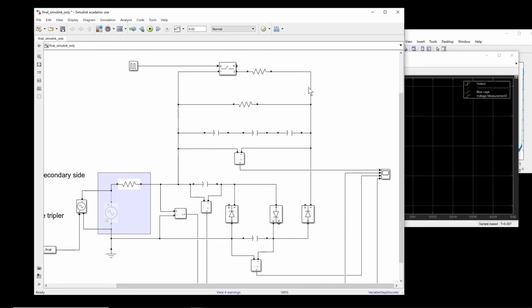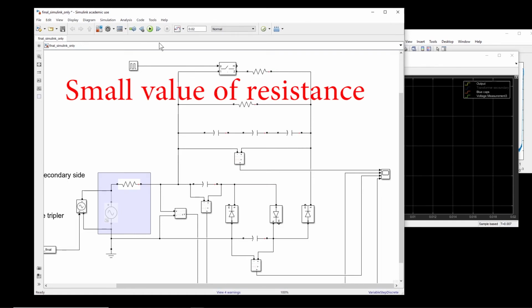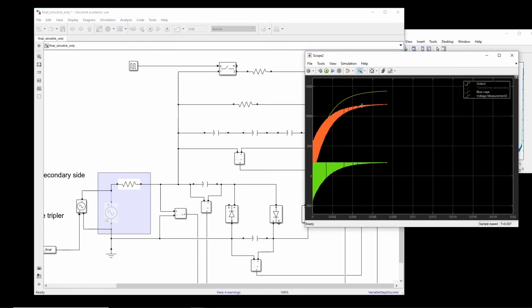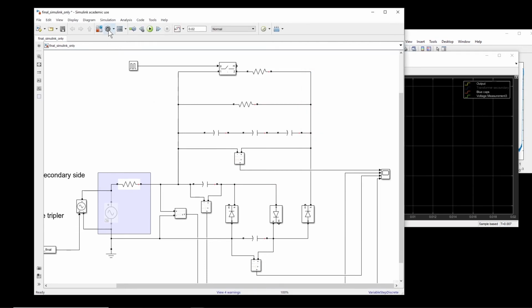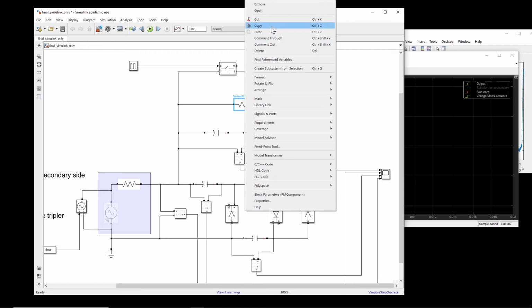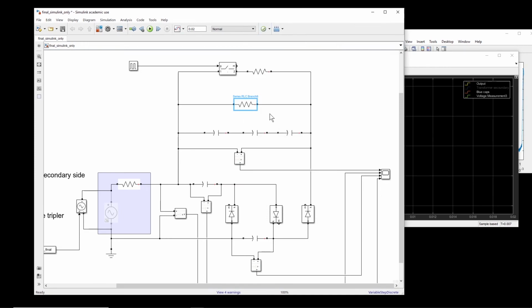If you want to measure the output of this generator, because here we have a 500 megaohm resistor, you must use a probe that has a much higher value than this, at least a high voltage probe with 1 gigaohm. Because if the probe you use has a small value, for example in this case, we notice that the voltage goes to near 1450 volts. But let's say if you use a probe which has 10 megaohms...